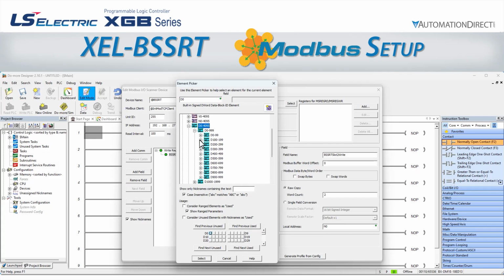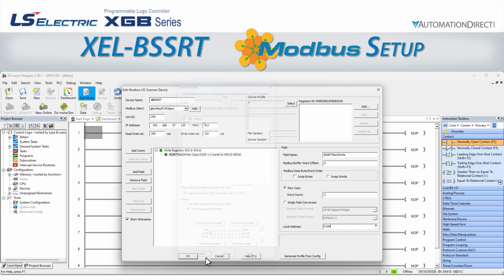Why don't we use D0, you ask? Often when programming in Do-more Designer, the system will grab the first register of a variable type, such as N, C, or D, for function block memory, communication settings storage, etc. It's best to be careful about manual variable assignment. Using a higher register ensures we don't accidentally step on a variable already being written to by another PLC function. If this was a large project, it might even be best to start manual variable assignment at D1000 just to be safe. Now that we have assigned our internal PLC variable mapping for this case, we can then click OK.